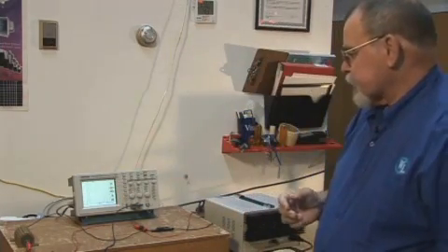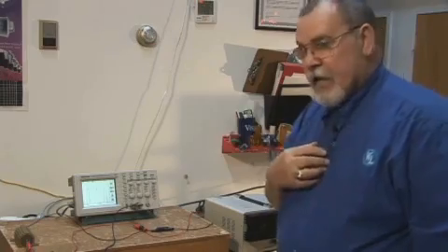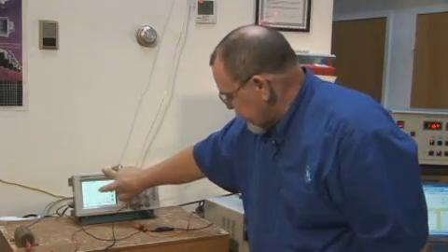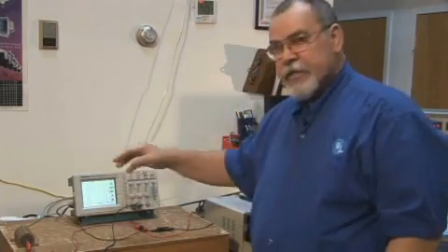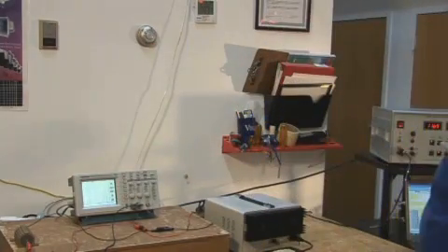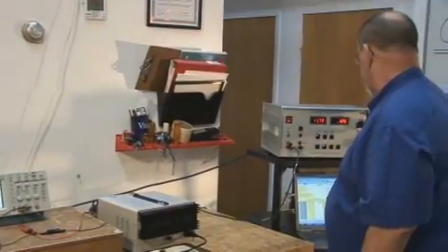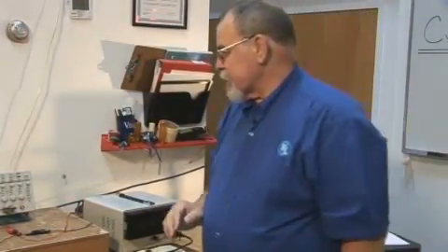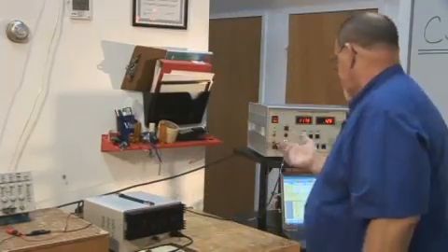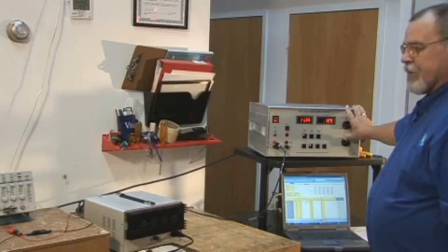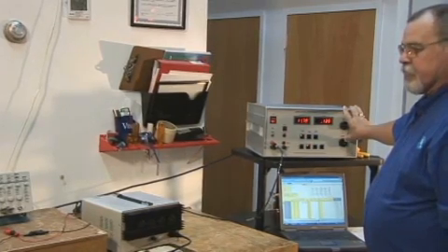I am seeing excursions in my eye, and I'm the one that's doing it, and when you're doing it, you'll have to determine, am I seeing a peak-to-peak excursion in excess of 17.85? And if you don't think you are, you're going to adjust the level a little bit higher to where you get at least that excursion. I'm getting that. I monitor the next frequency. I go to the next frequency point, maintaining this excursion level.